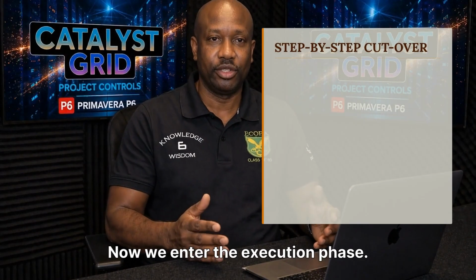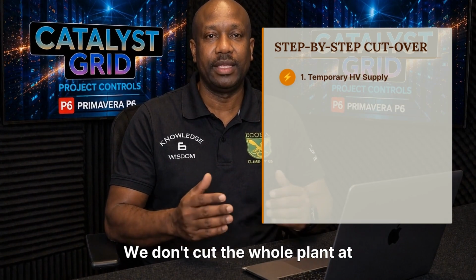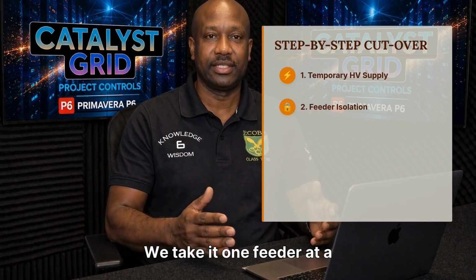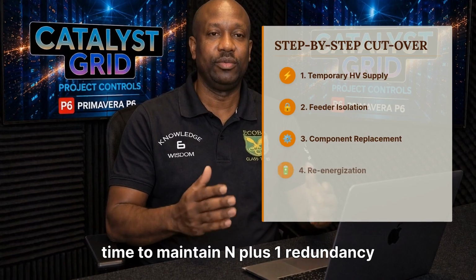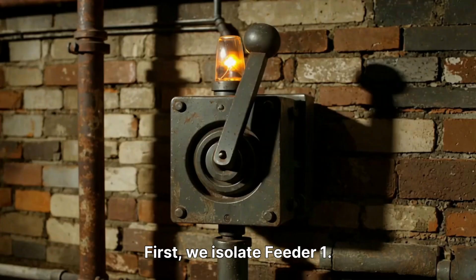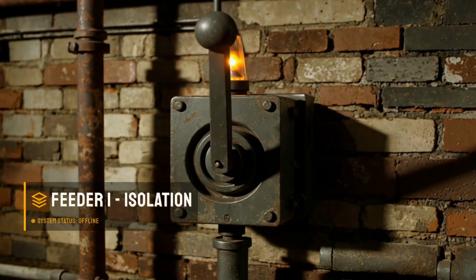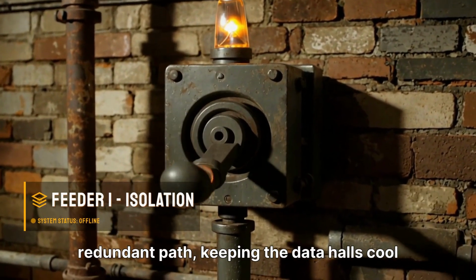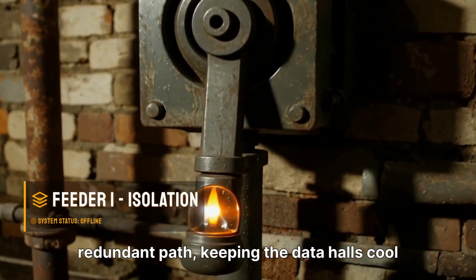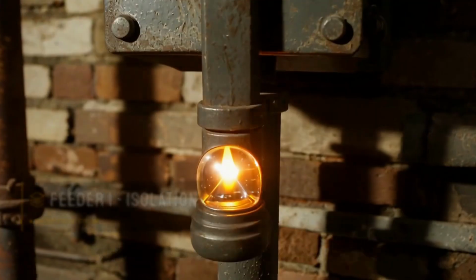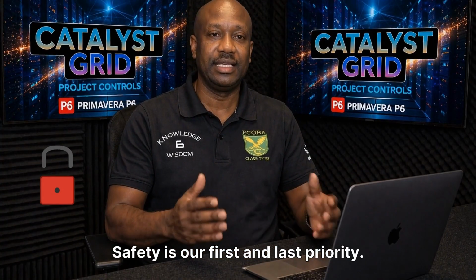Now we enter the execution phase. We don't cut the whole plant at once. We take it one feeder at a time to maintain N+1 redundancy throughout the process. First, we isolate feeder 1. The load is automatically diverted to the redundant path, keeping the data halls cool and the racks powered without a flicker. Safety is our first and last priority.